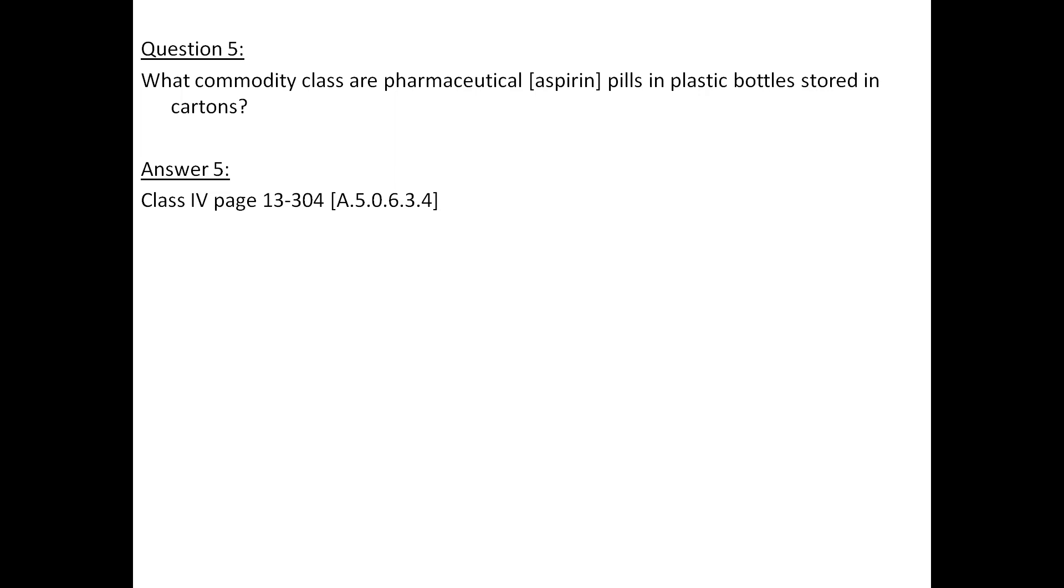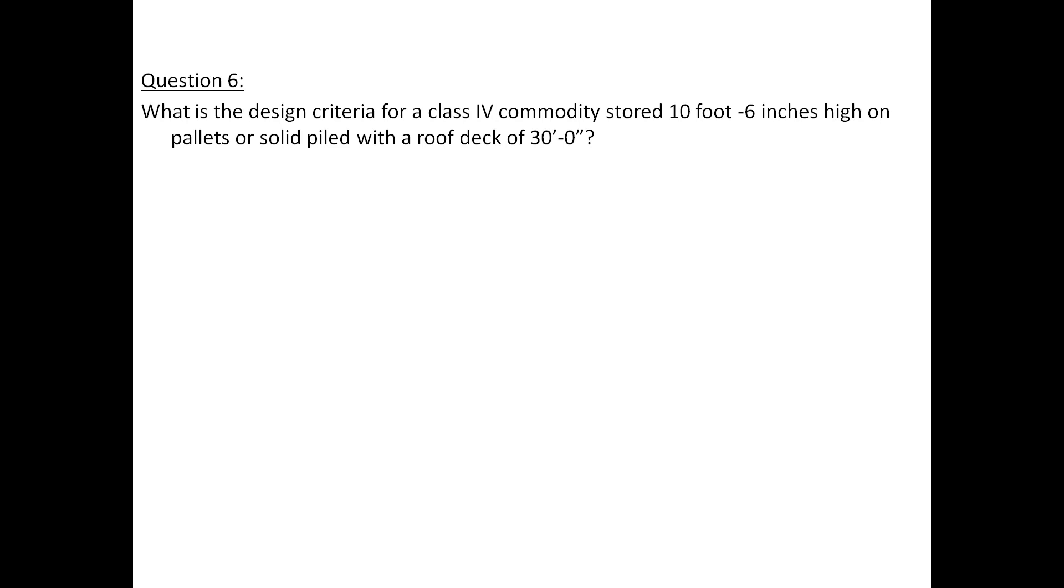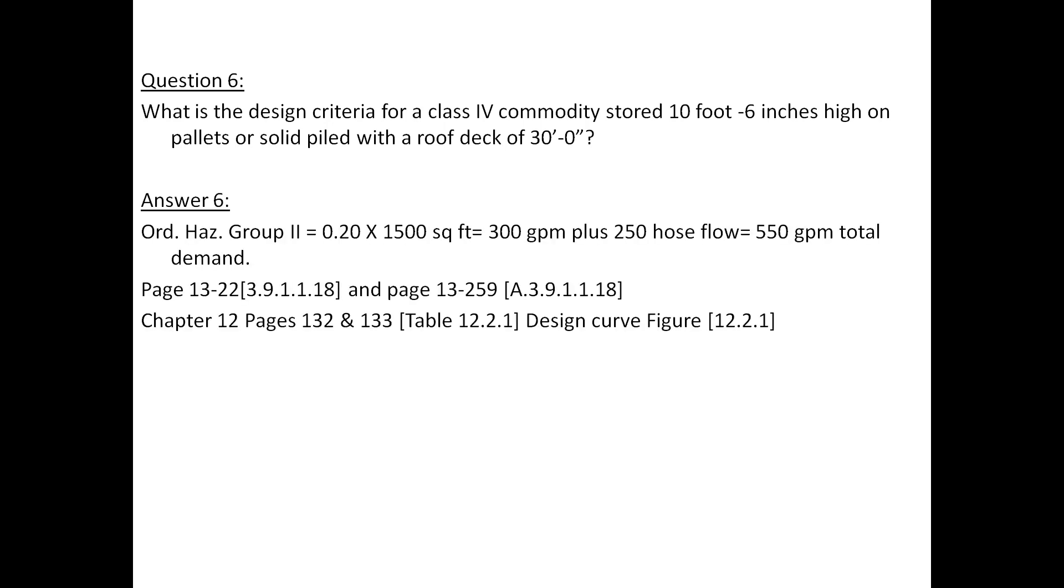Question number 6: What is the design criteria for a class 4 commodity stored 10 foot 6 inches high on pallets or solid piled with a roof deck of 30 feet? The answer to question number 6 is ordinary hazard group 2 which equals 0.20 times 1500 square feet equals 300 gallons per minute plus 250 for hose flow which would give us a total of 550 GPM total demand. Reference page 13-22 and page 13-259.